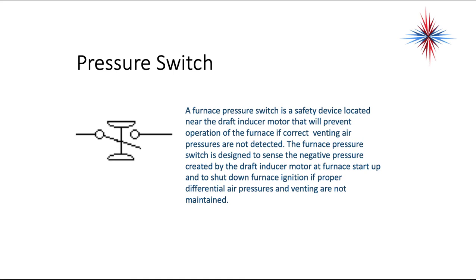In other words, if there's no flue, or the flue is blocked, it will prevent the furnace from operating. A pressure switch, all it does is work on the pressure differential between one space and another. It's either normally open or normally closed.